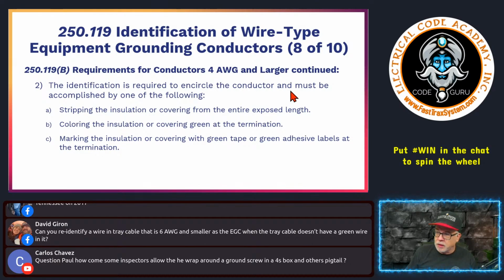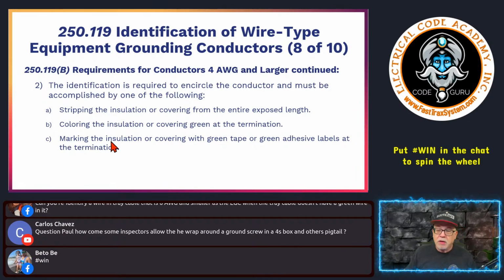You could strip the insulation or covering from the entire exposed length. So again, if it's, let's say, black, you could strip all of the insulation off of it, so that it is the bare conductor coming in, if that's being used as an equipment ground. You can color the insulation or covering green at the termination, just like that other picture did. They went a little overboard, but that's all that's necessary. Or marking the insulation or covering with green tape or green adhesive labels at the termination. Bunch of different options here for you to be able to do that. So you encircle it, but you also could simply remove the insulation.